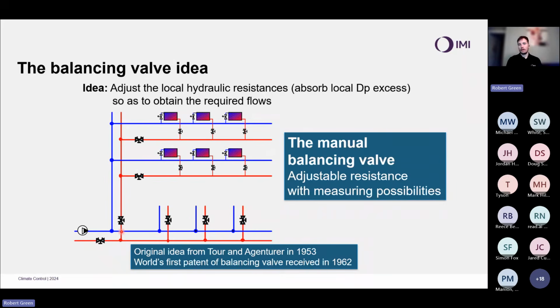Take the example of a big park with 3 routes through it, 2 long ways around the outside and a shortcut through the middle. All open, all easy to walk down. And I took 100 people and said, right, I want you to get from point A to point B. If I wanted an equal split, I would need to make it just as difficult or just as long to go through the middle, the shortcut, as it is to go around the outside. And in essence, that's what the balancing valve does.